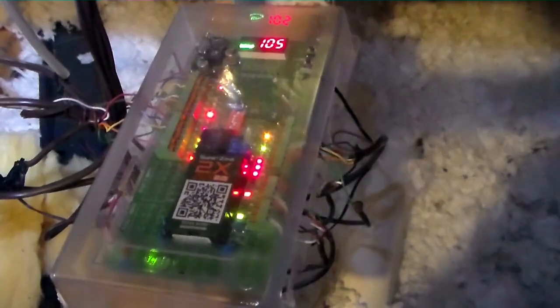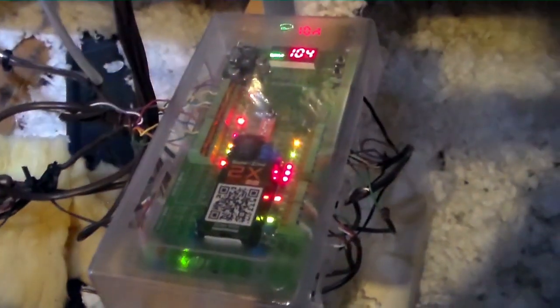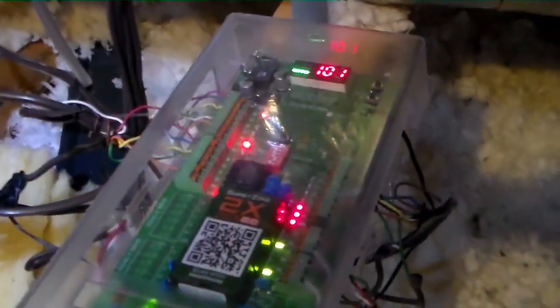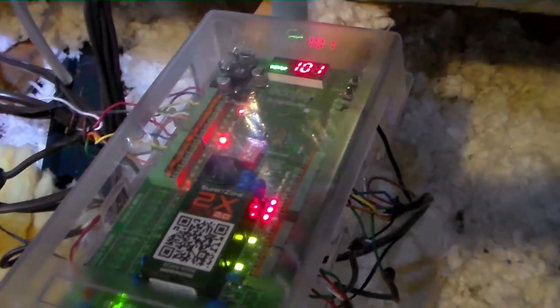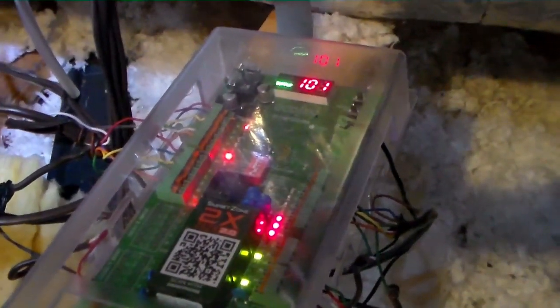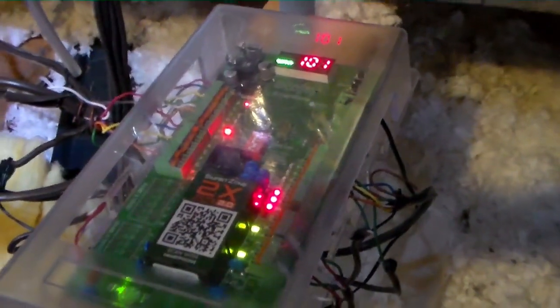Let me button this back up, and you guys can catch up with me after that. Our fan is operational. We're calling for cooling on zone 2, it looks like, and I'm sure the other zone will click on in a minute. So far so good. I'm going to button it up and we'll see how we're doing. Take an amp draw on that motor. In a few minutes we'll click back on. We'll have us a little bit of air conditioning.